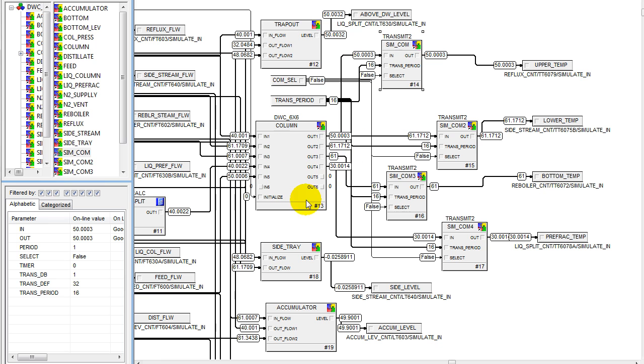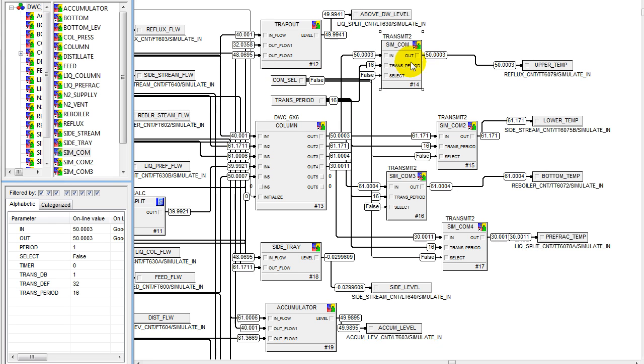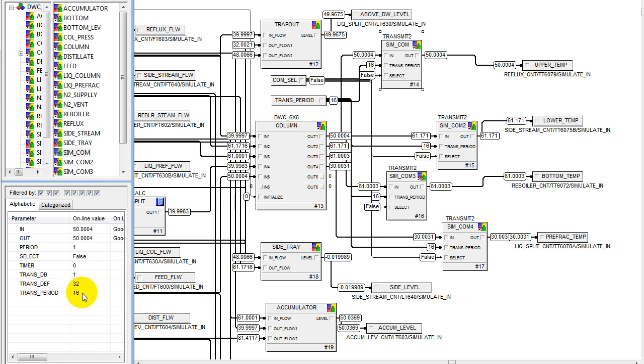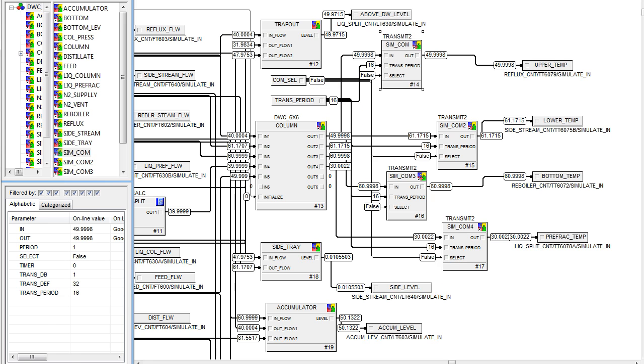Here is the simulation we're using to simulate the top temperature as well as all the other temperatures and flow loops of the process. We're not only simulating the process, but also wireless communication — in particular, windowed communication with a deadband of 1%, a period of 16 seconds, and a default of 32 seconds.